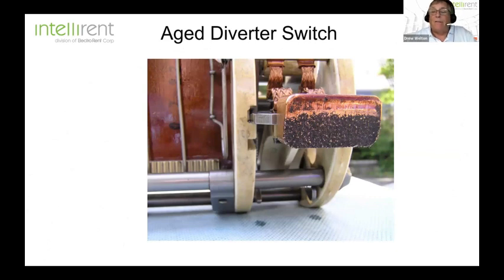And basically, this is just the look of an aged diverter switch, because over time there is arcing and sparking going on with LTCs under normal operation. Of course, if your cabinet is separate from the actual transformer, you can also do a DGA analysis of the oil on the OLTC as well.